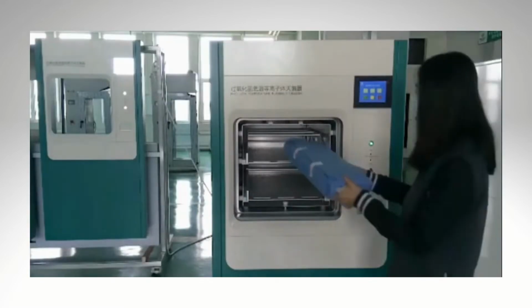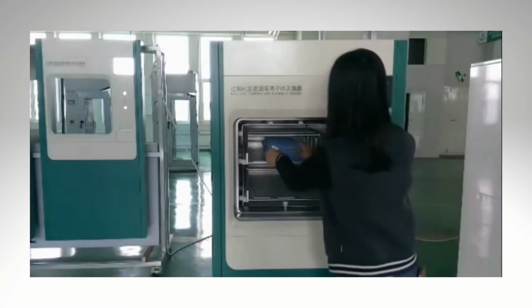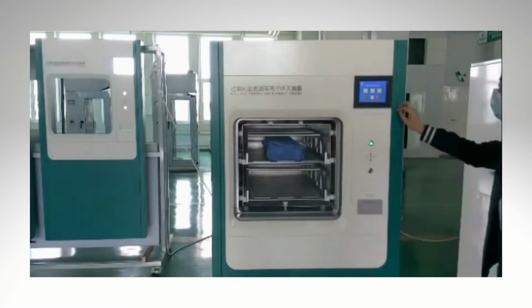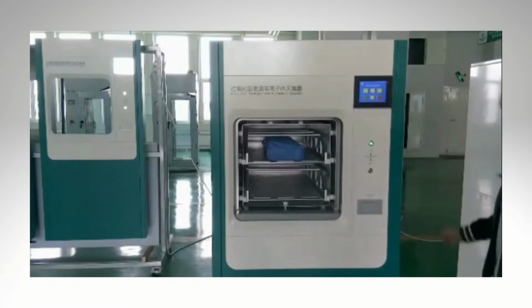This process inactivates microorganisms primarily by the combined use of hydrogen peroxide gas and the generation of free radicals, namely hydroxyl and hydroperoxyl, during the plasma phase of the cycle.